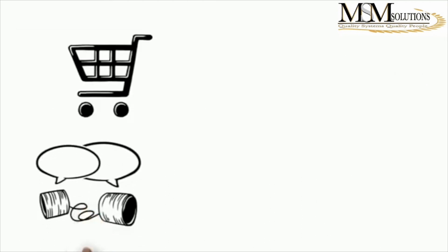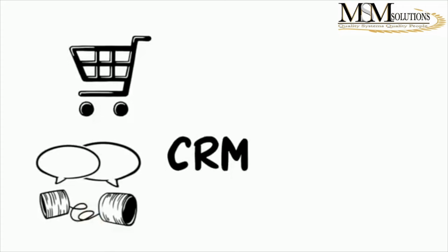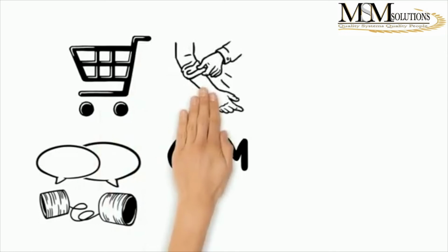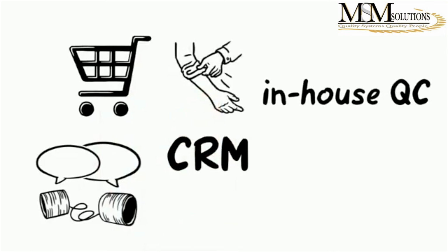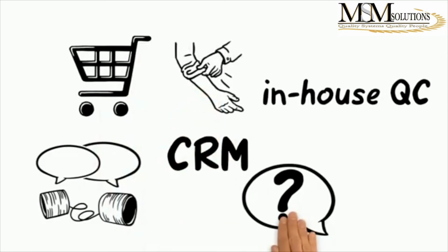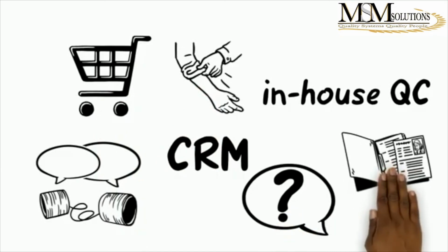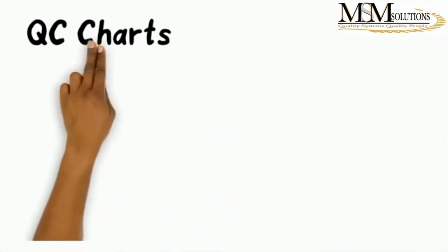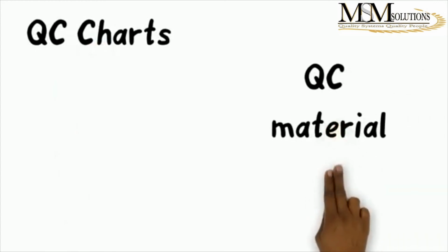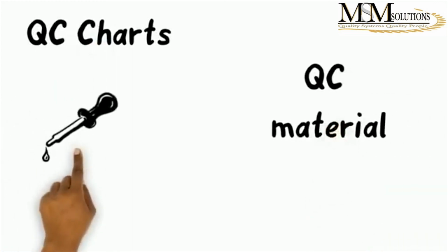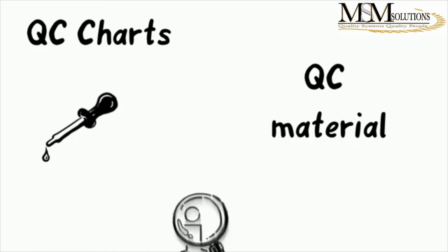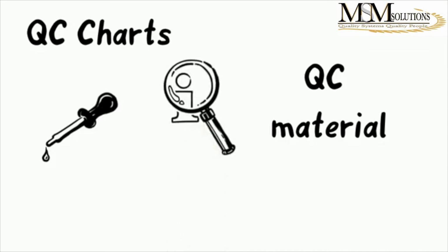So we've spoken about buying CRMs and what to look out for in terms of the CRMs we're buying. We've also spoken about how to prepare our own in-house quality control standards. The next question becomes, okay, now that we have this material, what do we use it for? What is its application? There are different uses of QCs. Some include preparation of QC charts. Remember, when you have a QC material, you will be analyzing it with your samples every day. So you can use those values to make QC charts. And there's certain information that you can then derive from your QC chart.